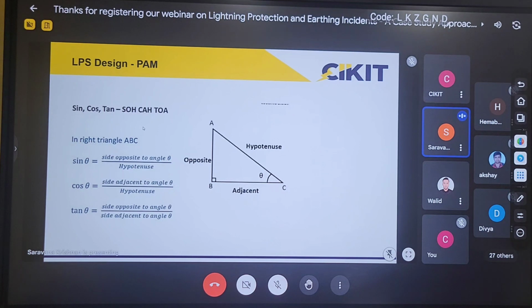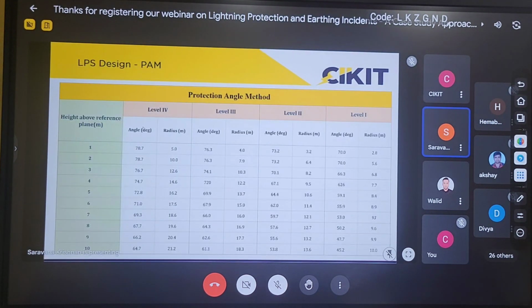the radius of protection. We have already done this calculation and arrived at a result for different heights. Here you can observe that for 5 meter height at level 4, the radius of protection will be around 16 meters. Similarly, if I am going for 15 meter, I have to extend a line from 15 meter, find the angle, and from that angle calculate the radius of protection.